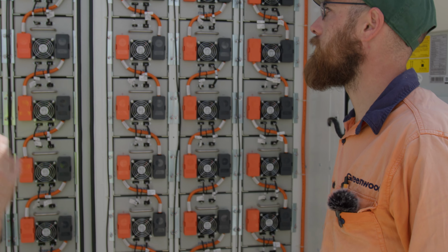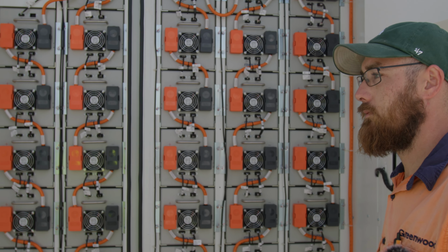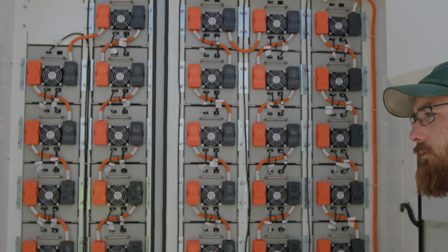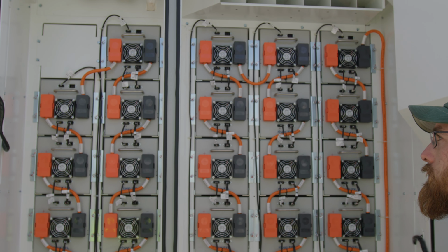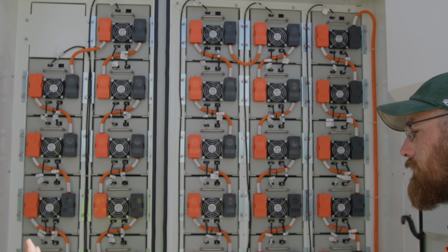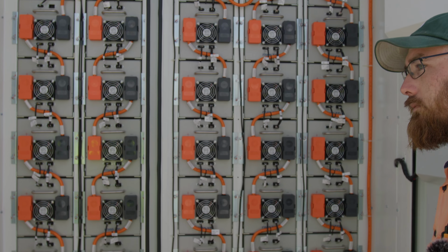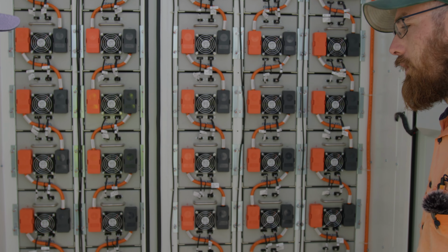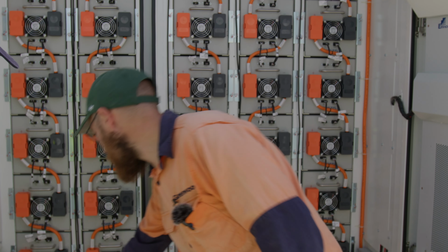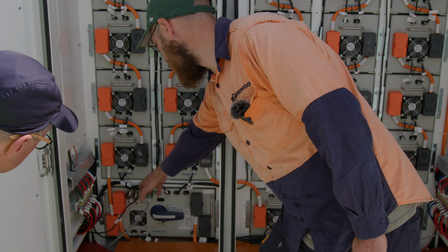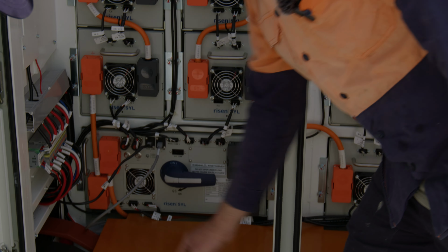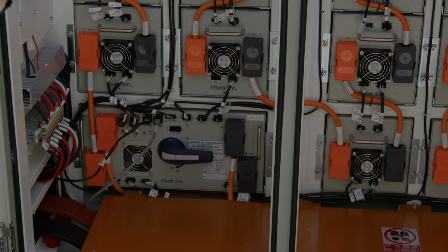Okay, so let's reiterate here. Each cabinet is simply a series connection between the battery cartridges, modules, whatever you want to call them, and then each individual cabinet is paralleled up to get that higher current. Correct, they're actually paralleled down here. As you'll see, you come out of the bottom of the main isolator here. These two cables connect onto the bus bars that run through the bottom and out into the next cabinet.